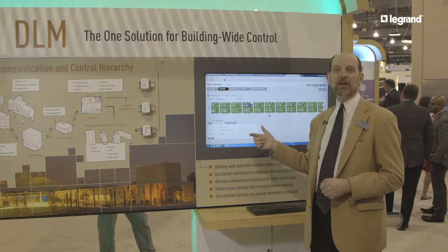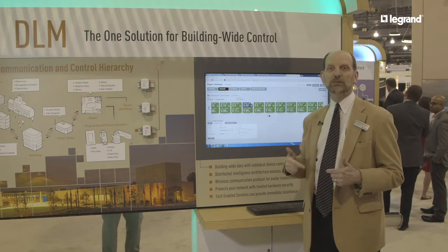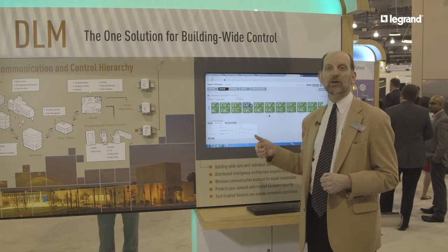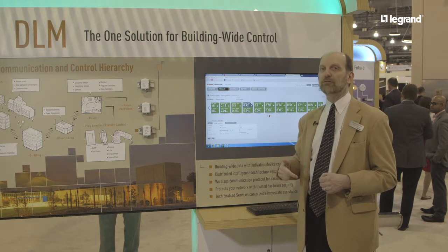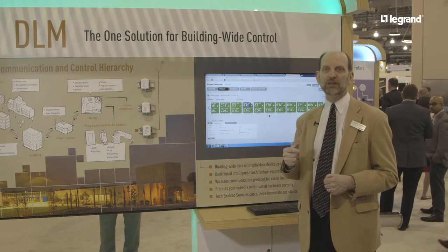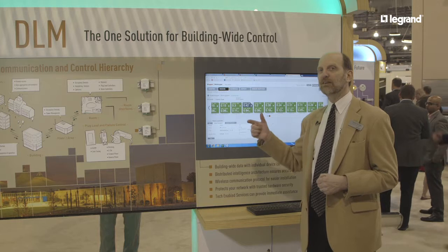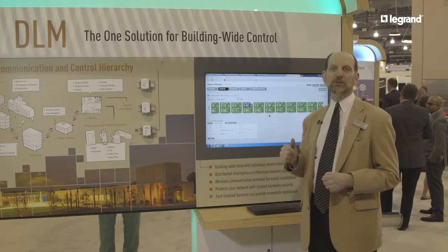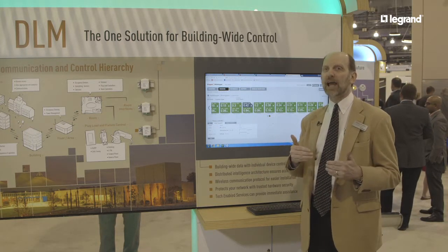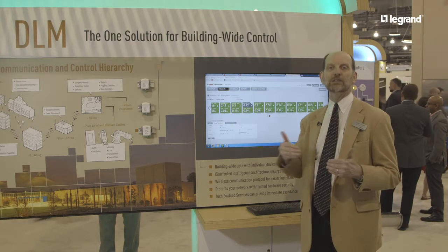As an example of some of the data that's really valuable, if we take a look at our segment manager interface, here you can see information for each one of the rooms. We're showing what the power usage is for each room, and then for each room we've also added one other field, which is the square footage. So we not only see the total power, we see the watts per square foot. Here we can gauge exactly how efficient any one room is against any other.